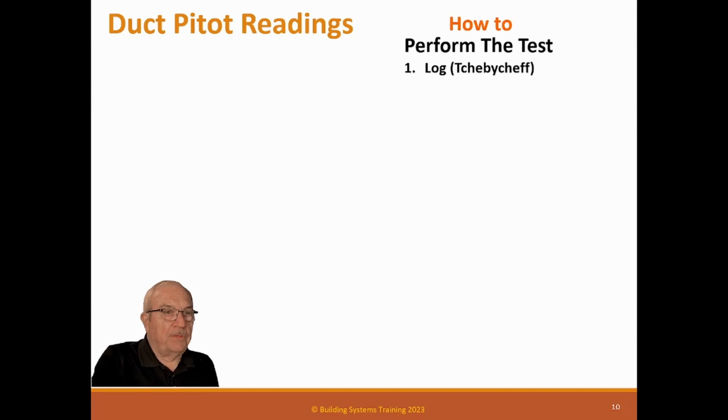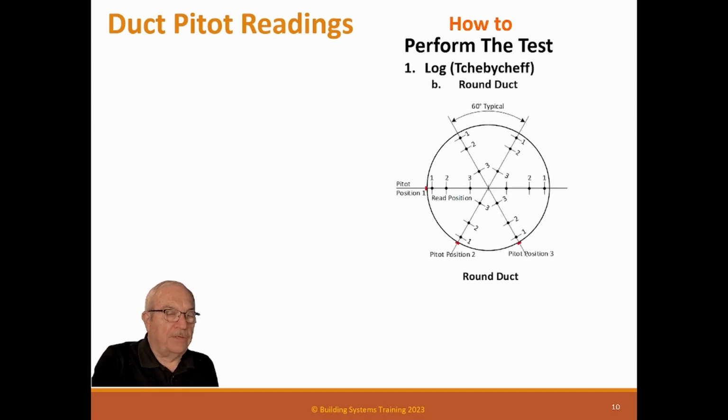So how to perform the test for the log Tchebycheff round duct. Now this one has a little bit of a problem because it has so many axes, and they're a lot harder to access. And this is actually why a lot of techs don't use the log method. It's a little harder to do in the field, and for the couple of percent accuracy it gains you, I don't think it buys you a lot.